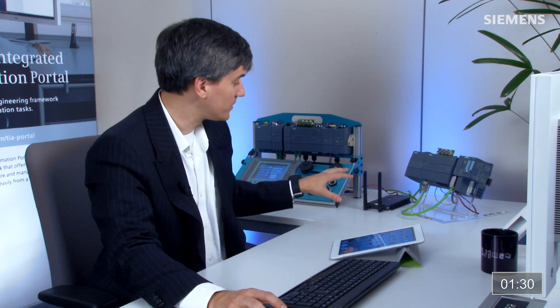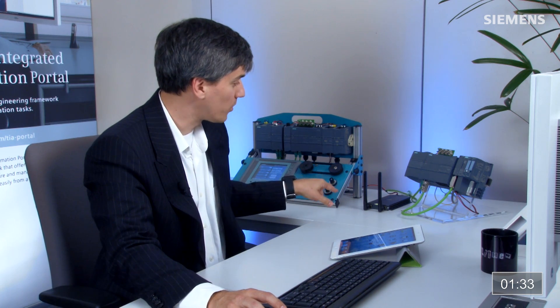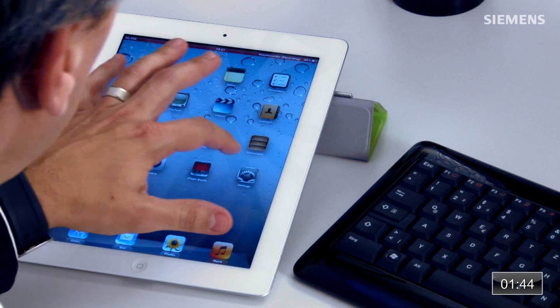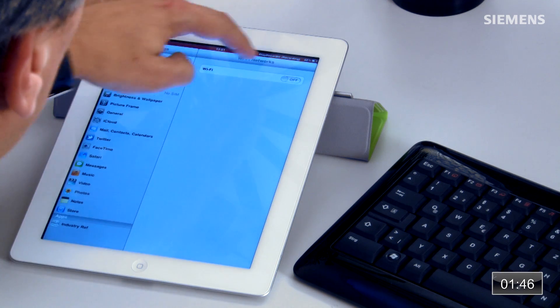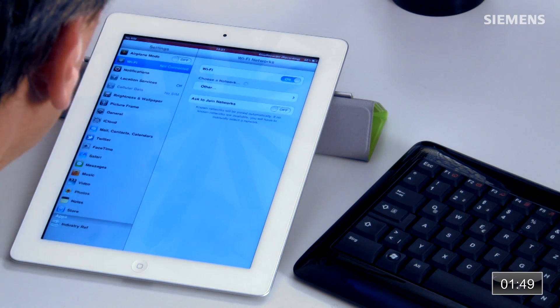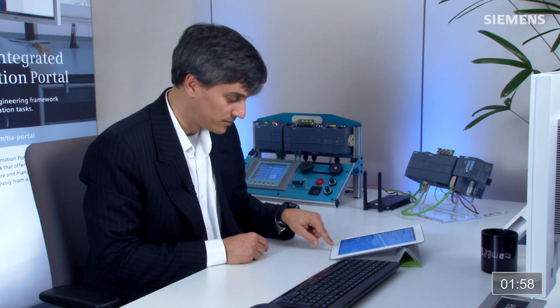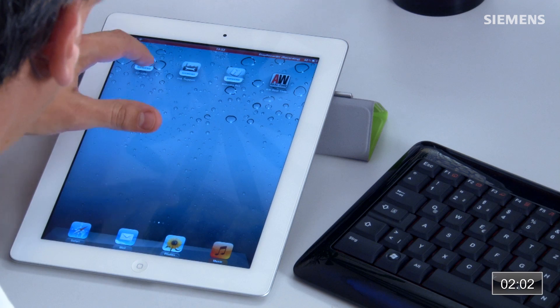Now, how about the smart device and an access point? I have an access point pre-configured with this other control station. I've also gone to the App Store and loaded the Simatic S7-1200 app, which is free of charge, to this iPad. The first step is to go to settings and enable Wi-Fi. It will search and try to find the access point — the S7-1200. That's the correct one. I set it up with a static IP address, just like the entire network configuration. So now we're online with it.